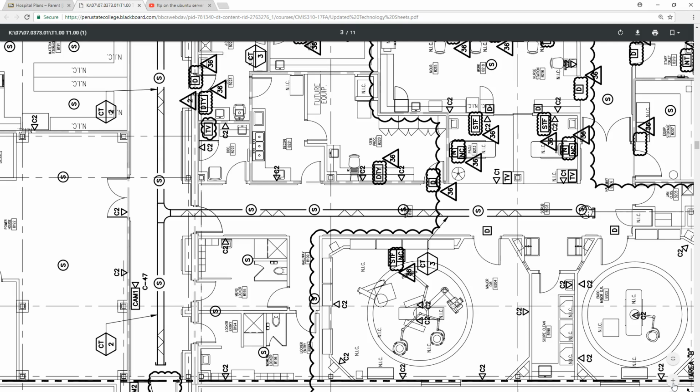But that's the typical data plan. So offices would look very similar. And here, notice we have data drops, data drops, data drops. One thing I will say, if you ever get involved in this position, a common cost item is, you might say, $100 a drop. It's much cheaper to put them in now, before they put up things like drywall, before they do ceilings, than it is to come back and have to add data to those positions, because it will greatly affect that.